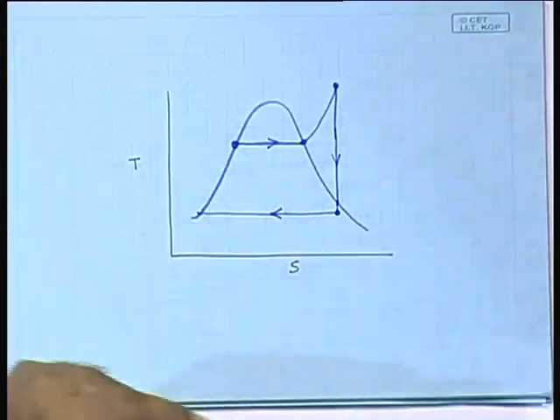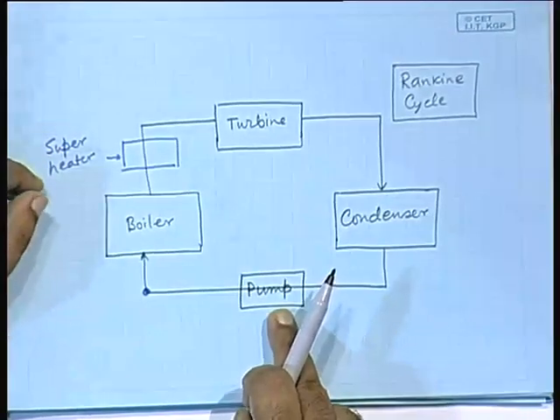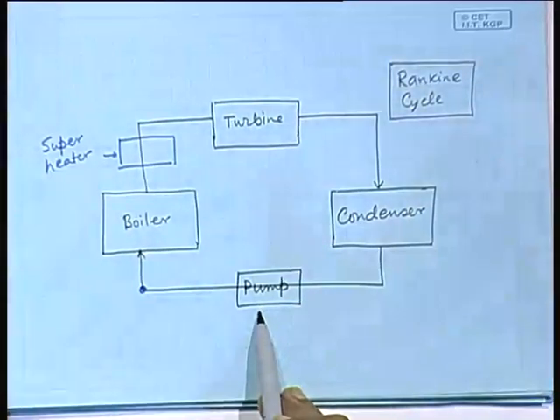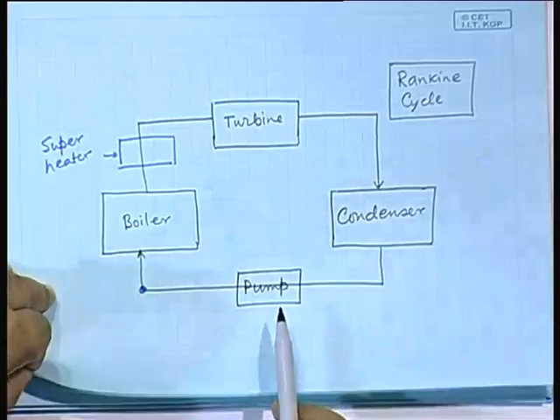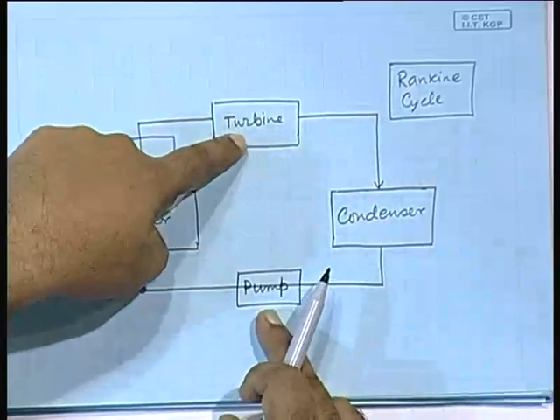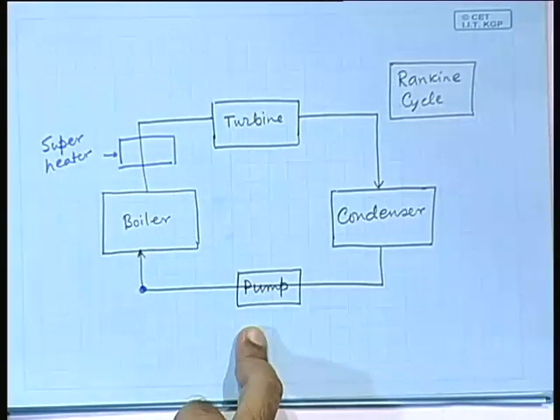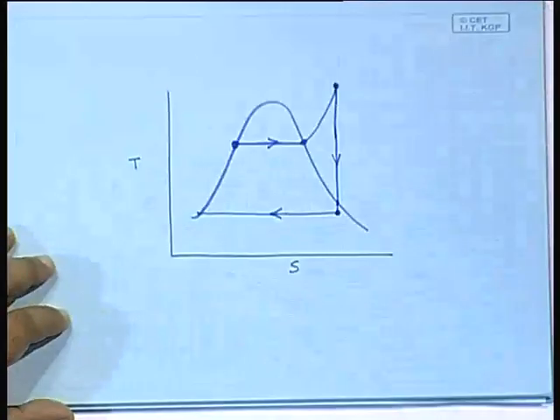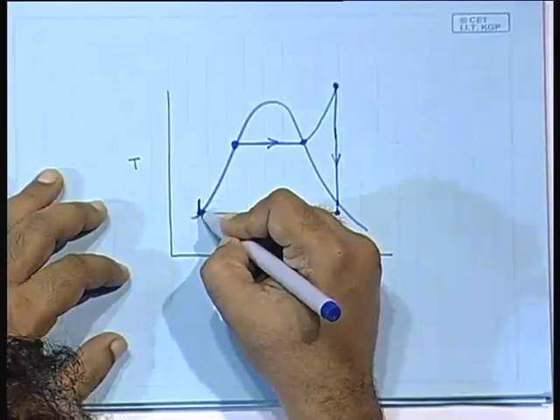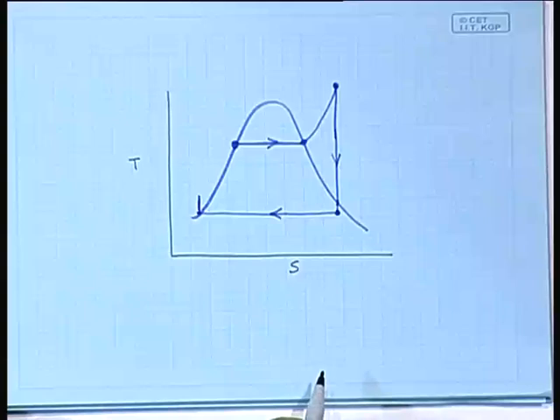Next, the water has to be pumped back. The pump, like the turbine, is not a heat-transferring device, so ideally it should also be an isentropic process with entropy constant. Since you are pushing work into it, there will be a slight rise in temperature. All pumps cause a small temperature rise. The pump requires far less power because it is handling liquid water rather than steam.